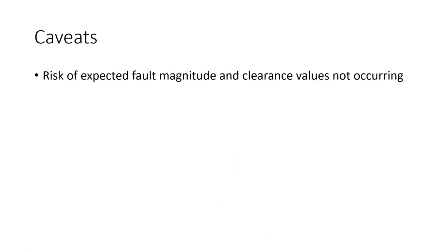There are several things to be aware of, though, when doing incident energy calculations and looking at protection. First of all, there's the risk of the expected fault magnitude and duration not occurring. Maybe the current might be a bit higher, which will then affect the clearance time. There's also the point of whether it's high voltage or low voltage. High voltage calculations tend to consider a very low impedance arc flash, and therefore we use the prospective fault level. And we obviously calculate the duration based off the circuit breaker or the fuse settings.